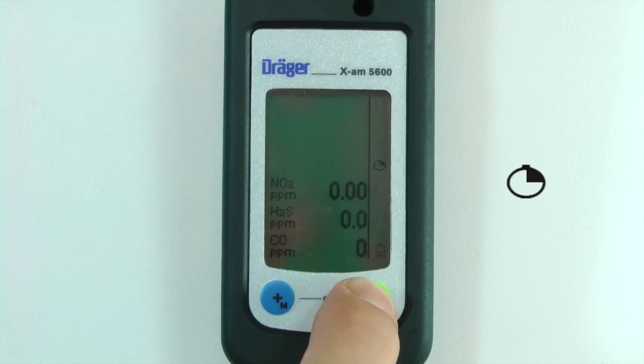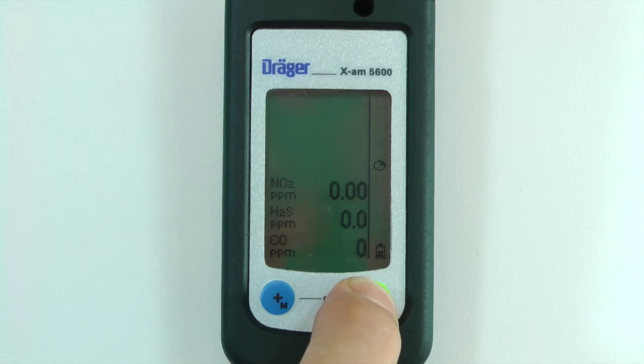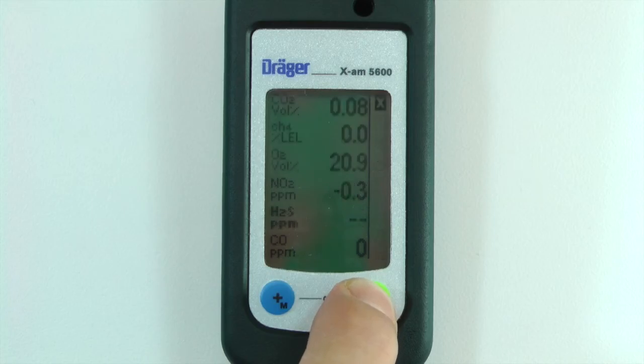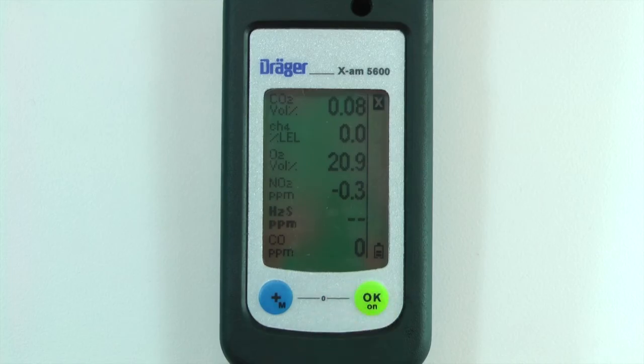Continuing to press OK cycles through STEL concentrations and the number of STEL alarms. Once all the settings have been cycled, the instrument will automatically return to Measuring Mode.